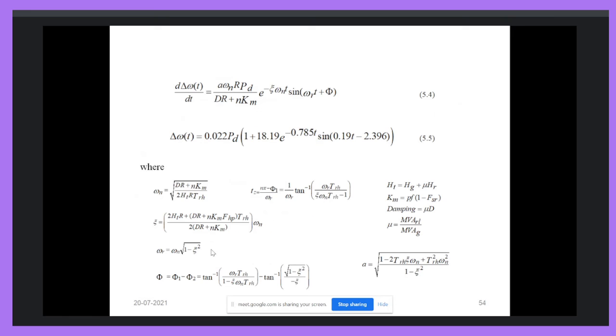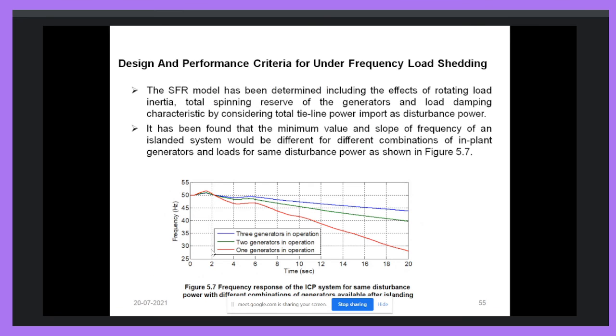Here we can see the different equations. This equation 5.5 is important because it shows the relation between the difference in load and generation, and the change in frequency. Okay, so as the difference increases, the change in frequency will increase. So we have to reduce this difference in load and generation. So to reduce the load and generation unbalance, we have to initiate load shedding. Okay, so to design performance criteria for the under frequency load shedding scheme, we have to perform system frequency response analysis, and on the basis of the system frequency response analysis, we have to design the load shedding technique. Okay.